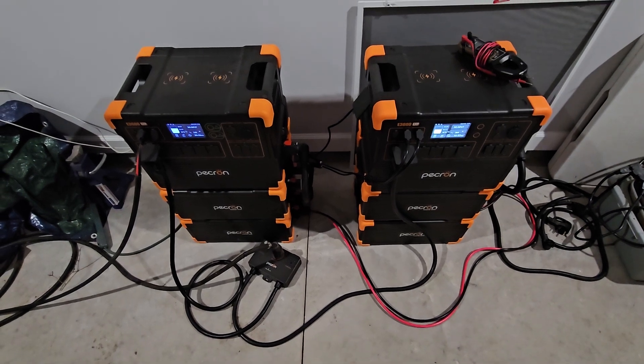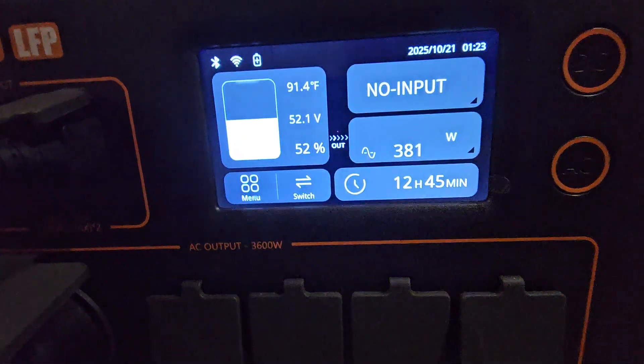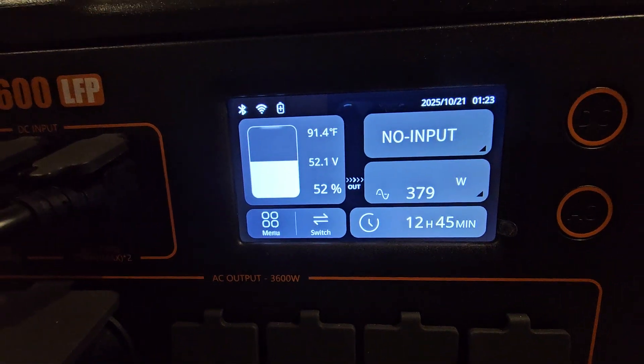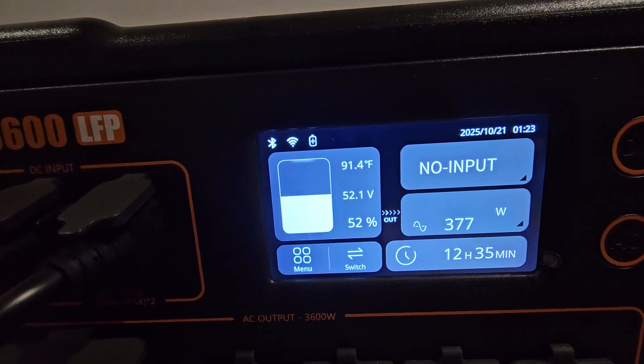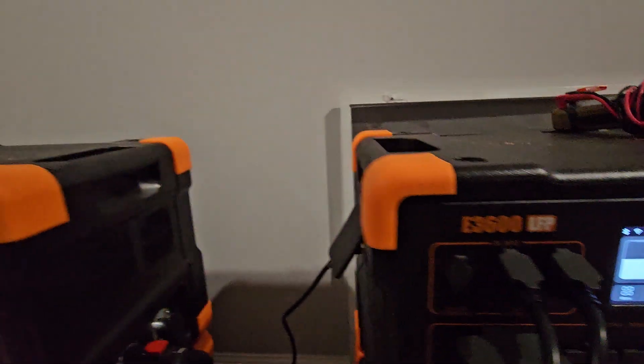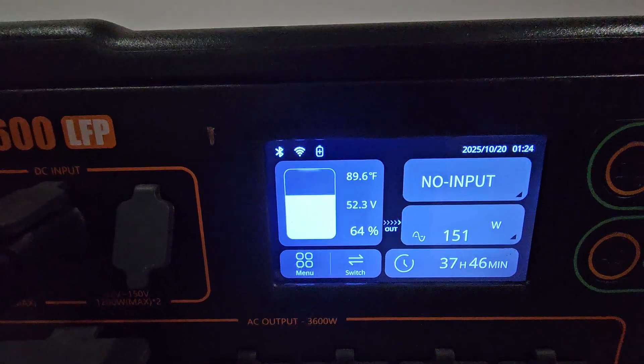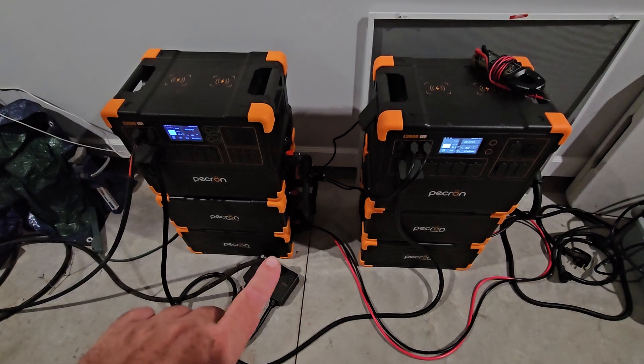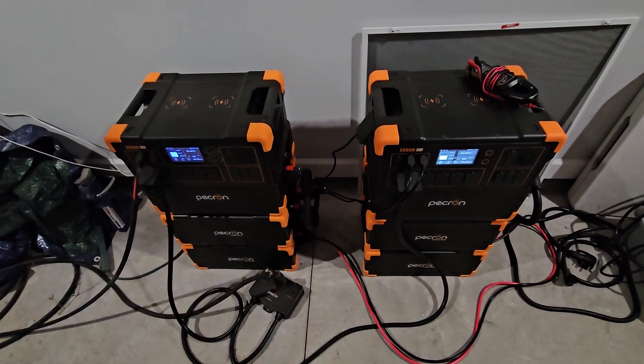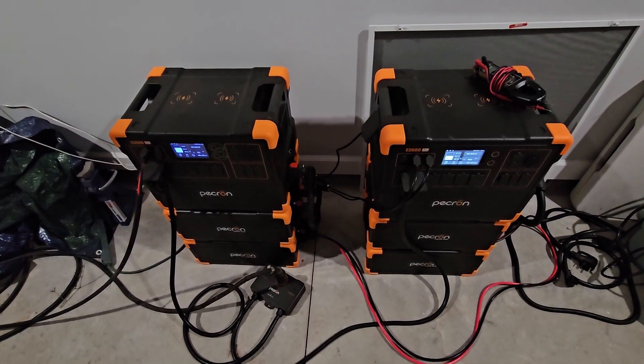As you can see, this power station here is around 52% — or ironically 52.1 volts — and this power station is at 52.3 volts or 64%. So they are not staying balanced as evenly as they were with the bonding cable going between the two host units.